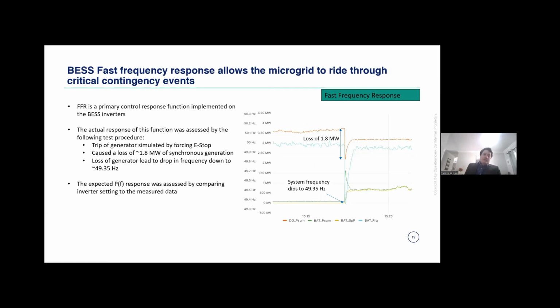Another critical aspect that we had to implement in this microgrid was the fast frequency response within the battery system. I don't want to go into too much of the definitions here, but essentially fast frequency response is a primary control response function that's implemented within the BESS inverters. It's not a secondary control response that is sent by the energy management system, which would lead to delays in response. It is something that's inherently set up within the battery system as a power frequency droop curve to allow very fast response from the battery in case of frequency deviations outside of the expected deadband.